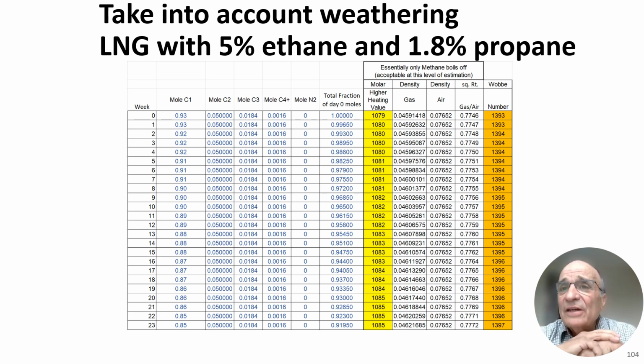But let's talk about most tanks which do not have nitrogen in the content of the tank. So you'll end up with the methane boiling off preferentially. And when that happens, you're left with more ethane and more propane left behind. So what does that do? It increases the higher heating value over a period of time, and it also increases the Wobbe index.